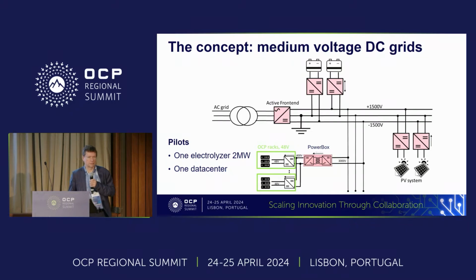So what is the concept? The concept is that we use a medium voltage DC grid to distribute the power to the racks. So at the input we have a standard transformer, then this is normal, then we have an active front end. Actually this is a big rectifier which is producing a medium voltage DC grid, and this medium voltage DC grid we decided to use is plus minus 1.5 kilovolts.